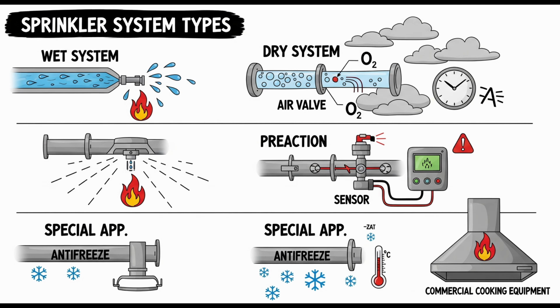Are there any other exceptions to these standard piping valve chamber requirements? Yes, the standard notes that these specific rules don't apply if the system uses an alternative engineered approach. This involves using an automatic pressure pump or device that actively maintains a higher pressure on the antifreeze side of the system than on the water supply side. Pushing back against the supply pressure. Yes, and this active system must also include provisions for automatically releasing solution if needed for thermal expansion, and provisions for automatically supplying more premixed solution if needed due to thermal contraction. This describes a more complex active pressure maintenance system as an alternative to the passive components, like expansion chambers or relief valves. An engineered active system instead of passive components.